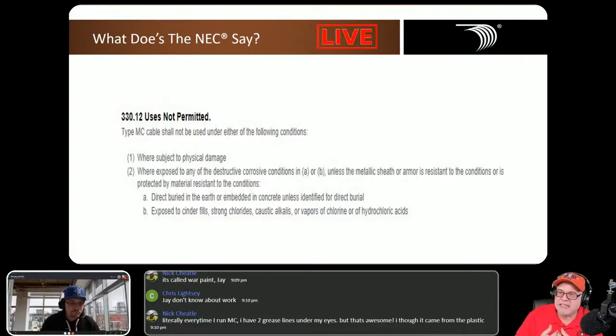I did a test for 18 months where I put PVC jacketed MC in a vacuum chamber with hydrochloric acid to see what would happen. Nothing happened, the PVC was fine, the armor was fine. But I had a control sample right next to it, regular MC with no jacket. In less than two weeks it started turning white, turning to powder, and by about four months in it was corroding. So that PVC material is very protective for corrosive conditions.